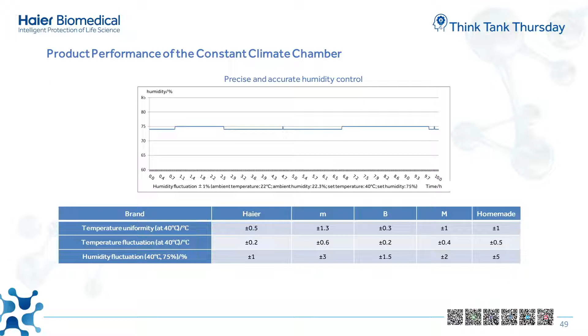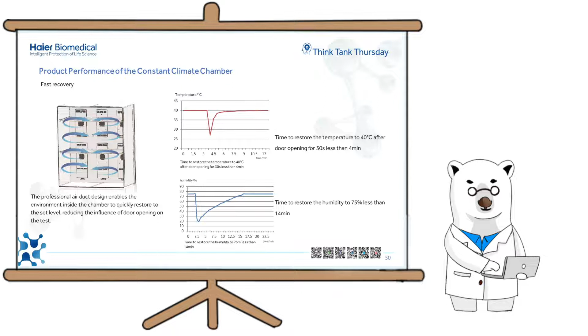Another important parameter of this chamber is the recovery time after opening the door for 30 seconds. Our professional air duct design enables the environment inside the chamber to quickly restore to the set level, reducing the influence of door opening on the test. The time to restore the temperature to 40 degrees after opening the door for 30 seconds is less than 4 minutes, and the time to restore the humidity to 75% is less than 15 minutes.